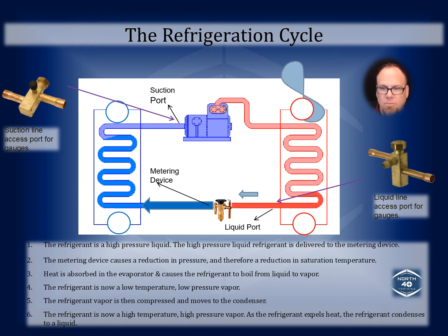And that's important because as it meters it going through the expansion valve in this case, or piston in other cases, it separates those molecules into individual molecules, so that way the droplets of refrigerant can absorb heat on all sides, which maximizes efficiency. And by the time we get to the last pass of the evaporator, we should have absorbed so much heat from the environment it's sitting in that all of the refrigerant in the last pass of the evaporator and beyond is now boiled into a vapor. And then it's going on to the compressor.